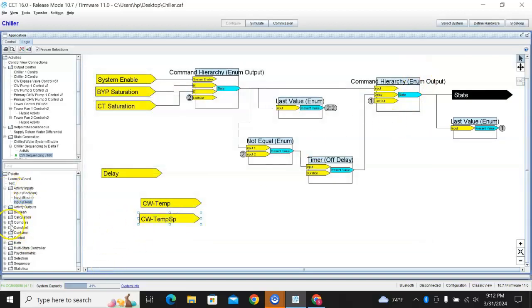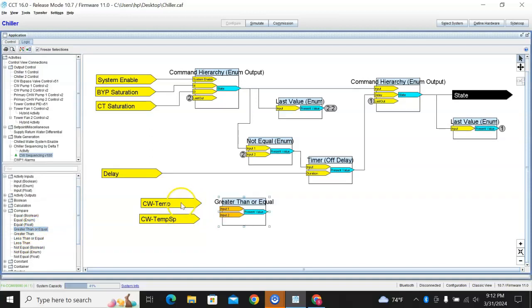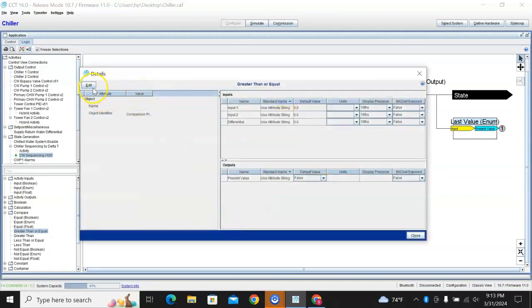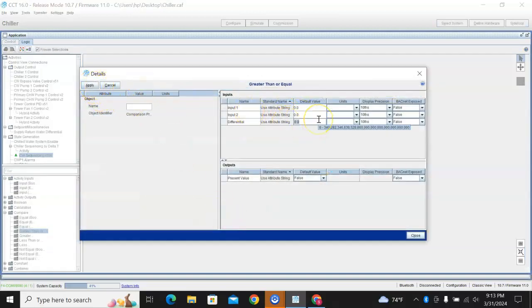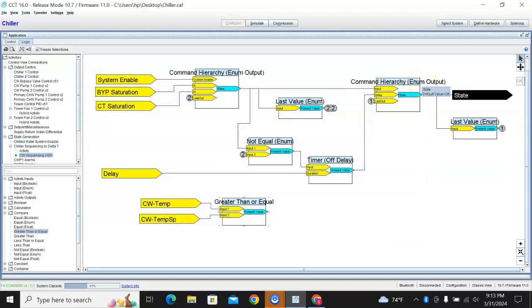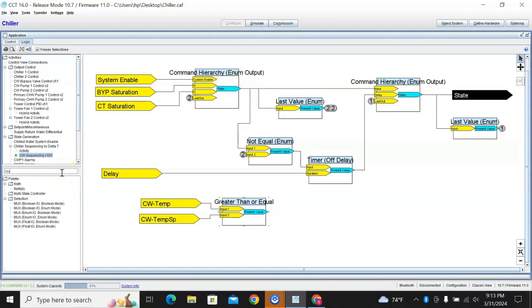Okay, we'll do a compare. Bring a greater than or equal to over here, temp on top, set point on the bottom. If the temp is greater than the set point, we'll throw in a differential here. We'll put 3 degrees. Again, you can play with that. Command hierarchy block, I could use one of those, I think it's just easier to use a mux block in this case.